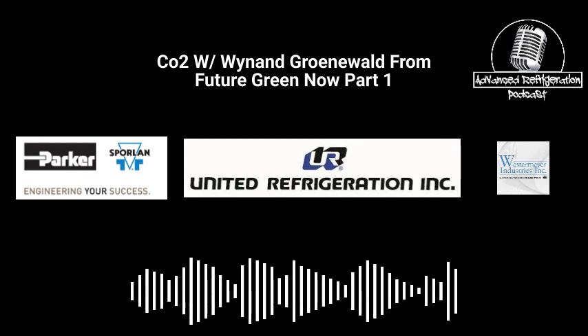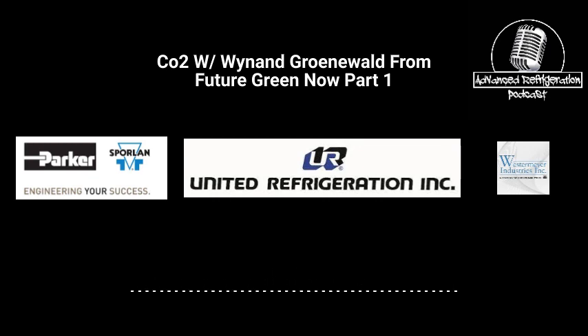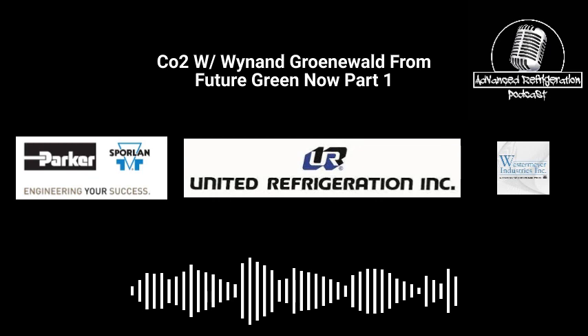I never realized that. Kev, is that a new thing for you too? They get quieter, and they quiet down a lot more when there's more caseload. But in the beginning, when the case is empty, the superheat's kind of hunting all over the place. So yeah, that makes sense.